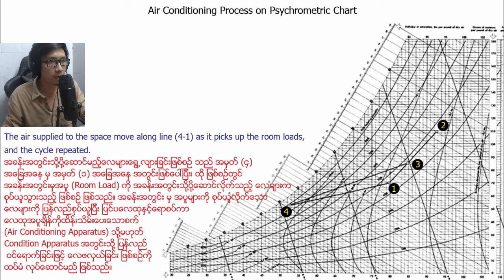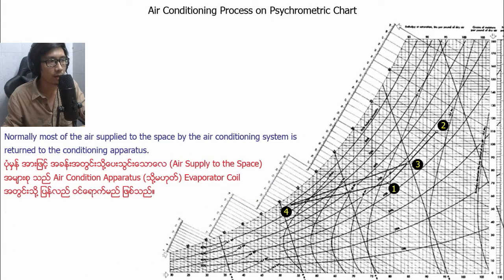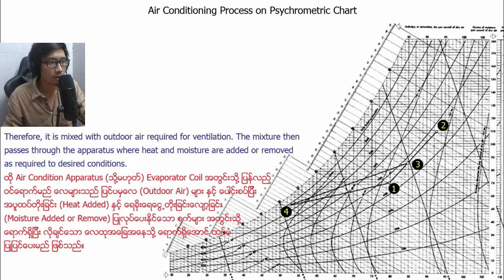The air supplied to the space moves along line four to one as it picks up the load, and the cycle is repeated. Normally, most of the air supplied to the space by the air conditioning system is returned to the conditioning apparatus. Therefore, it is mixed with outdoor air required for ventilation. The mixture then passes through the apparatus where heat and moisture are added or removed as required to achieve the desired condition.